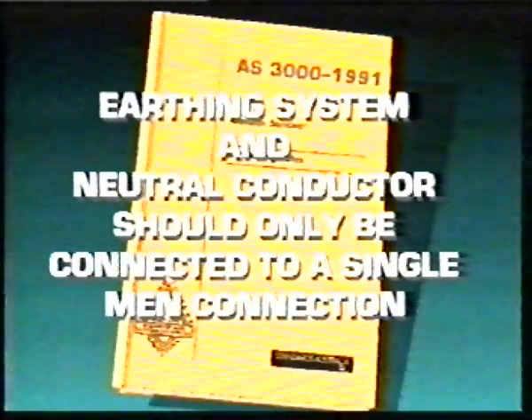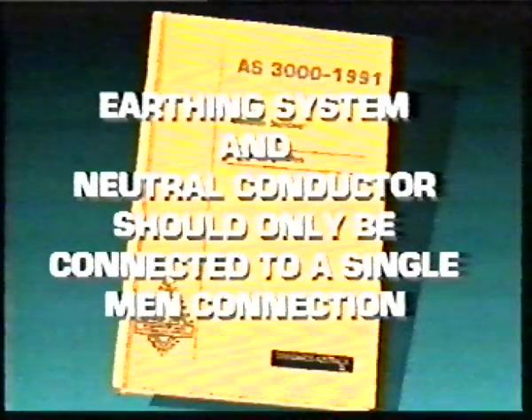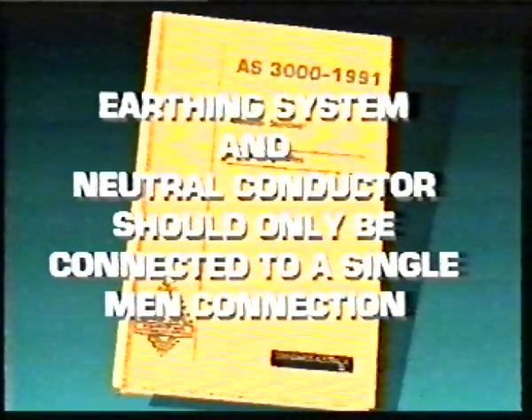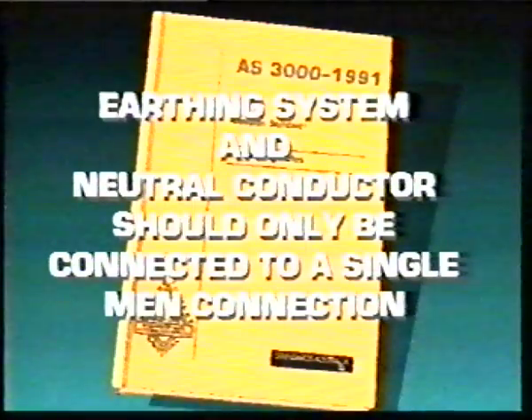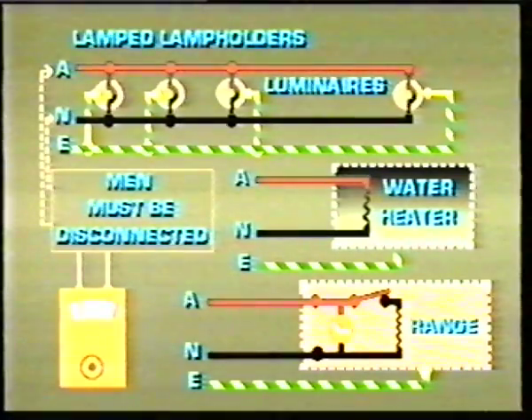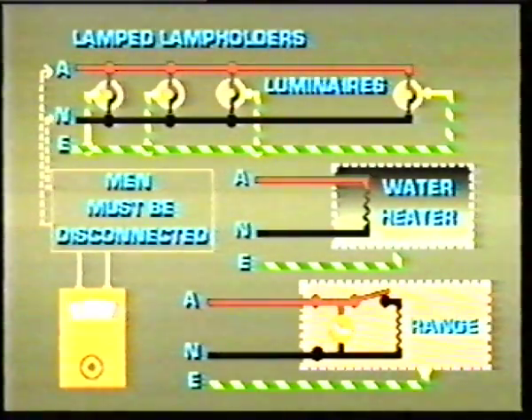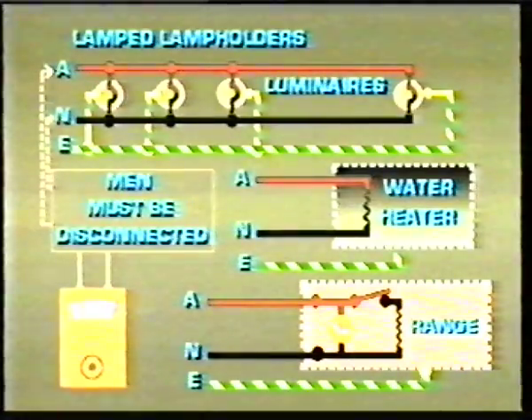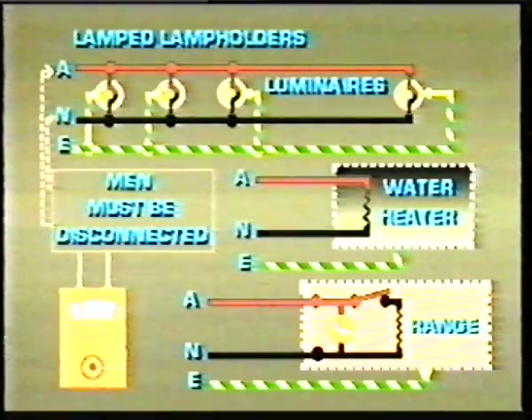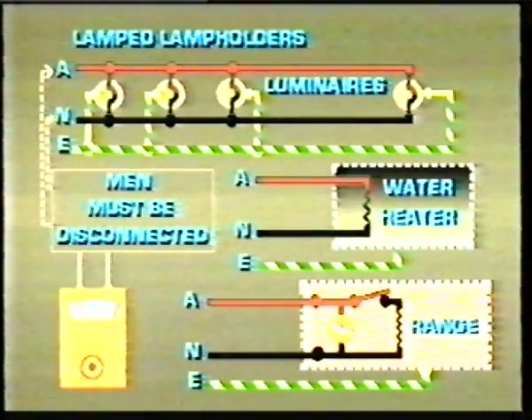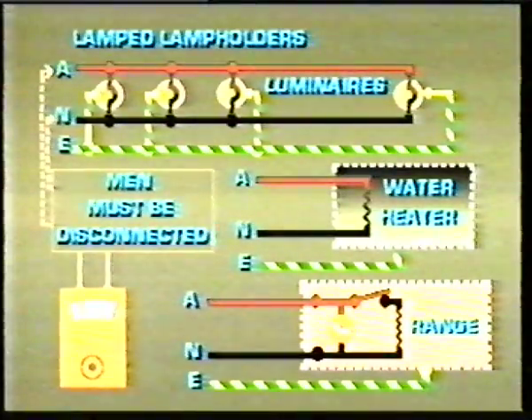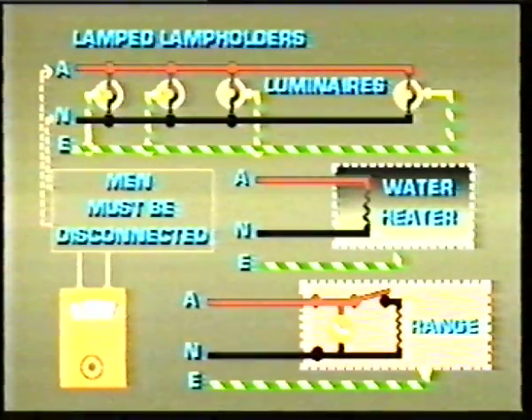AS3000 requires, under the MEN method of earthing, that the earthing system and the neutral conductor only be connected to a single MEN connection. Testing should indicate that the earthing and neutral conductors are separated throughout the installation and correctly connected to equipment. The test is generally performed on appliances and luminaires connected to fixed wiring, the contacts of socket outlets, and the contacts of unlamped lamp holders.